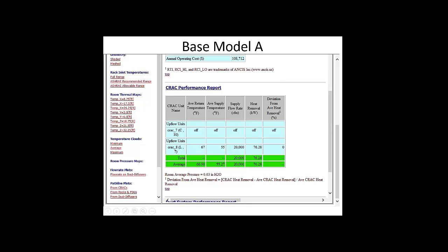That's just really hard on a cooling unit. If the inlets are near 70, you want the returns to be 90. You want a 20-degree delta across your CRAC unit, and preferably move it up so that the return is up in the 80s, 85, 90.